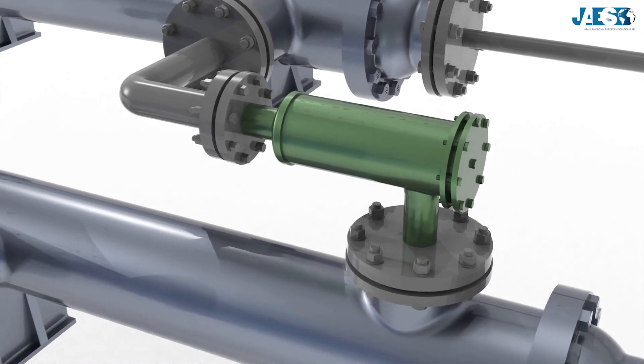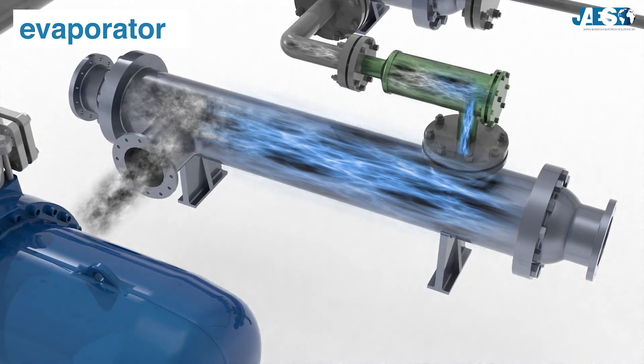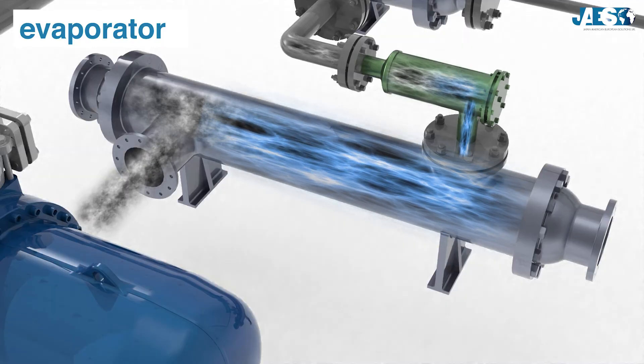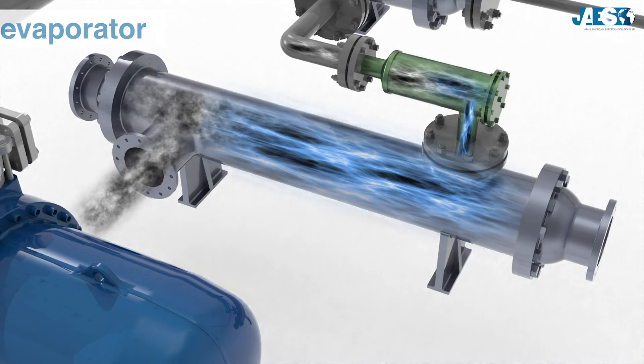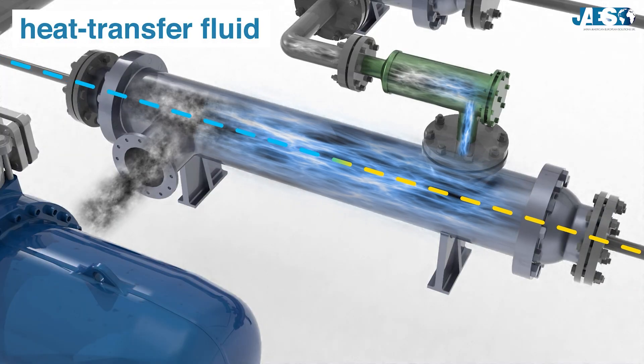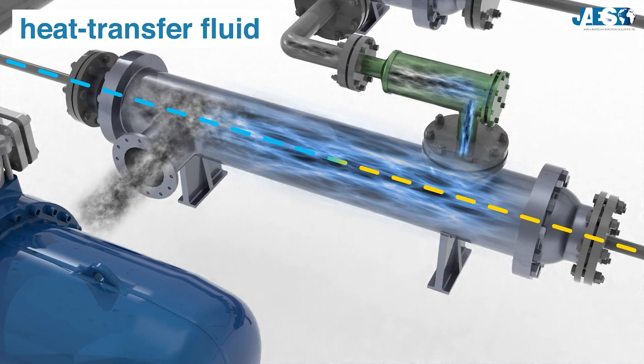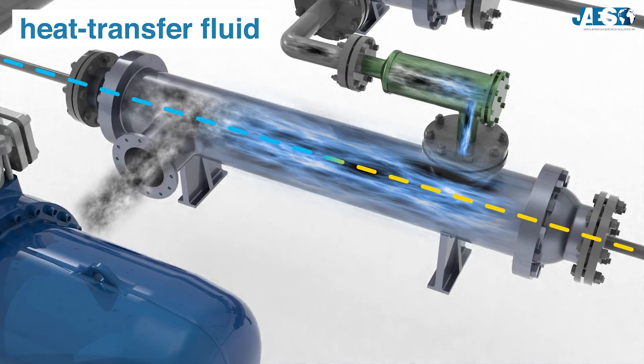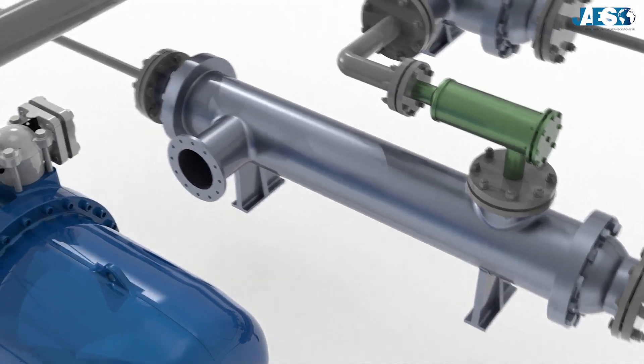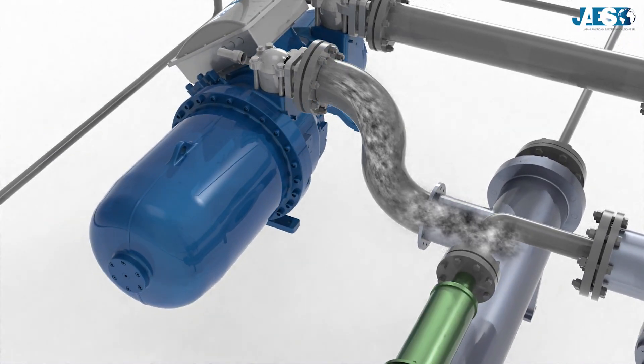These new characteristics enable the coolant to absorb the heat in the refrigerator, achieving the required temperature by passing through the evaporator. The evaporator also functions as a heat exchanger, using the refrigerant fluid to lower the temperature of the water circuit, called the heat transfer fluid. Although maintaining its temperature, the refrigerant fluid absorbs the heat and consequently evaporates. It then returns to the compressor to close the refrigeration cycle and repeat it continuously.